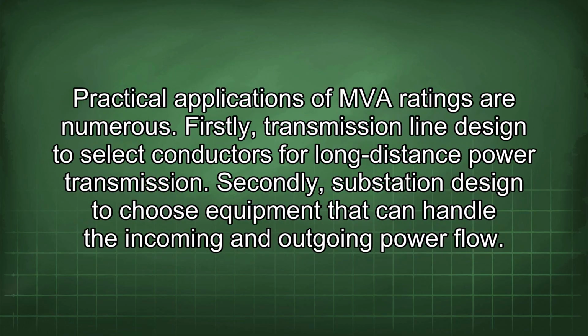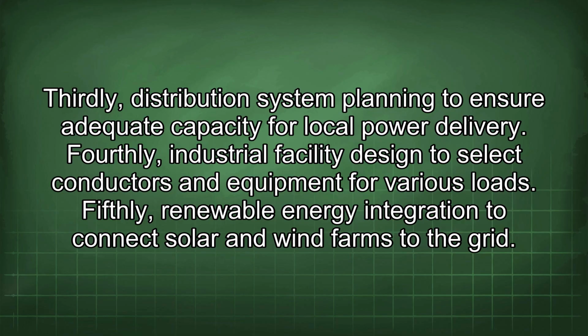Practical applications of MVA ratings are numerous. Firstly, transmission line design to select conductors for long-distance power transmission. Secondly, substation design to choose equipment that can handle the incoming and outgoing power flow. Thirdly, distribution system planning to ensure adequate capacity for local power delivery. Fourthly, industrial facility design to select conductors and equipment for various loads. Fifthly, renewable energy integration to connect solar and wind farms to the grid.